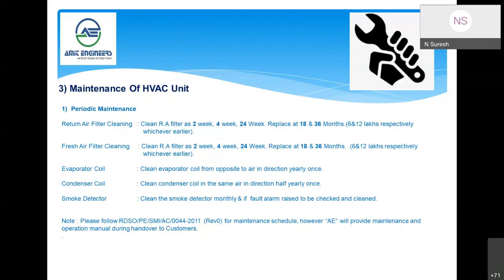Similarly, the condenser coil. Even though it is not in the comfort area, that is the evaporator compartment, it is in the condenser area, the condensing unit area, where a clean coil will give better condensation, designed power consumption and better cooling.